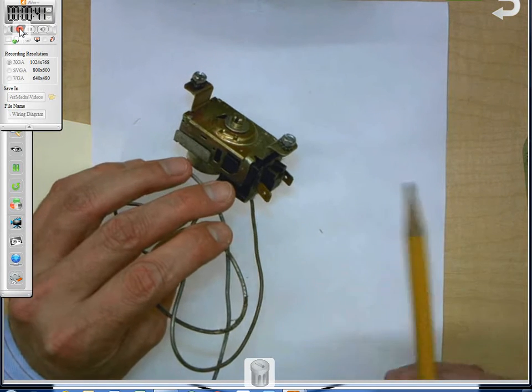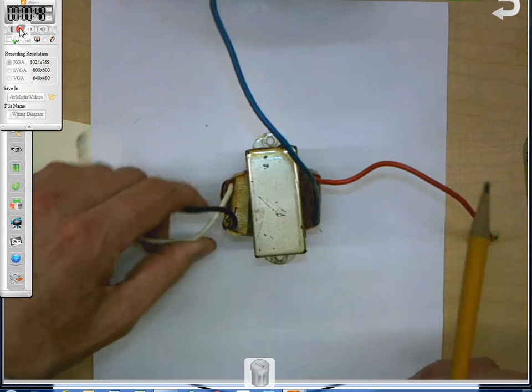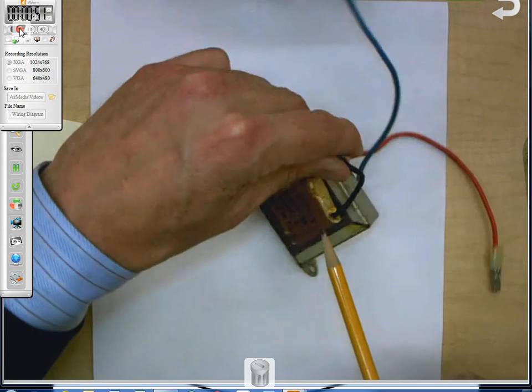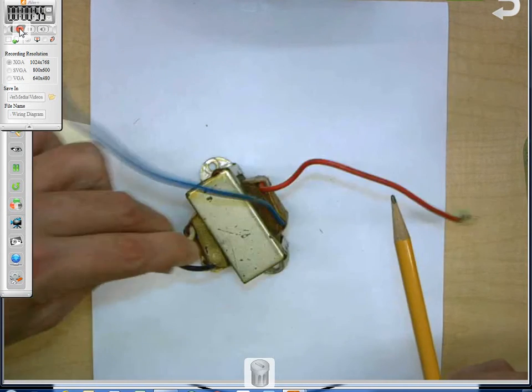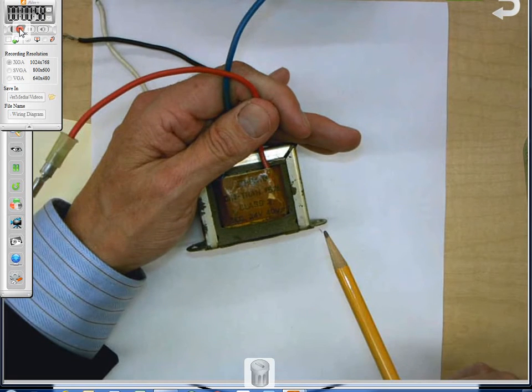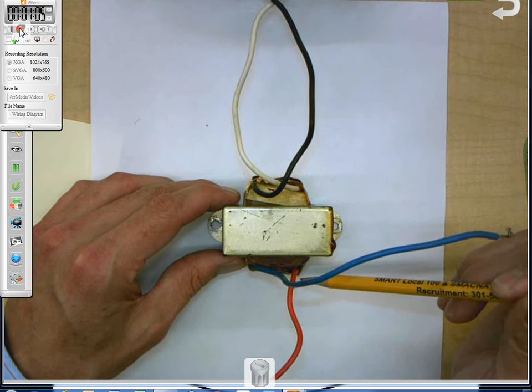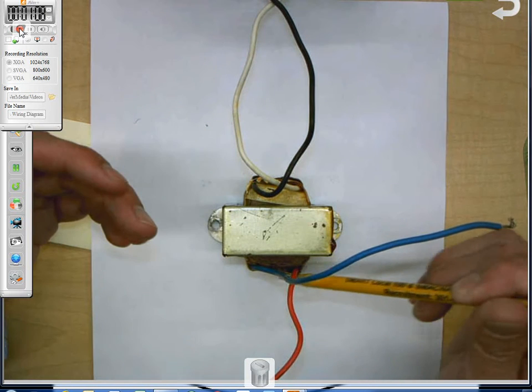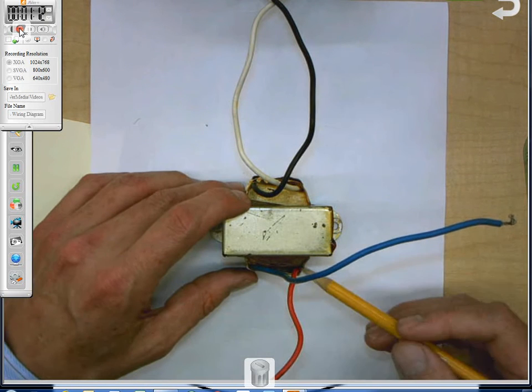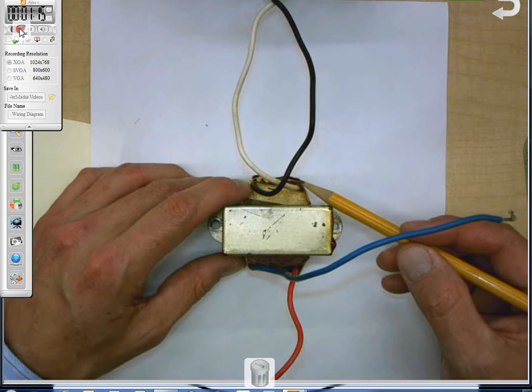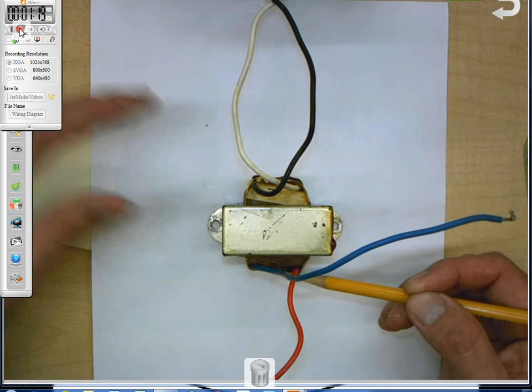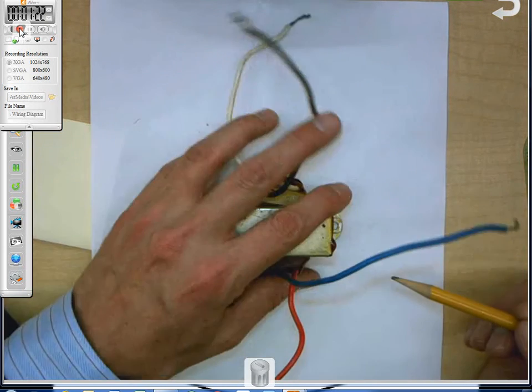Again, before I get into it, some of the loads we're drawing, this shaded fan motor does not have a capacitor. So all you need is a neutral and a hot. So there's no cap on that. Here's your thermostat, cold control some people call it, but it's a thermostat. So it's going to be a single pole switch that closes on temperature rise. Your transformer.